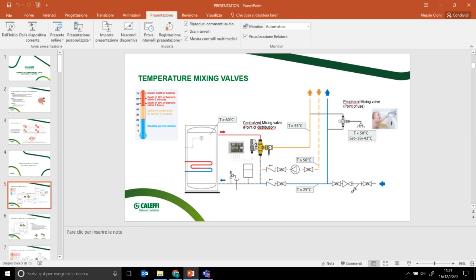In case instead this valve fails the thermal disinfection, and it might happen, for instance, let's suppose disinfection time has come and we want to have 70 degrees all over the building, but the water in my storage is too cold, the water will not perform it. So this failure will be recorded and, in the case of a BMS, also reported. This message will be brought to the person responsible for Legionella treatment, and he will react accordingly, maybe increasing the hot water temperature in the storage and performing the disinfection again. Everything will be recorded.